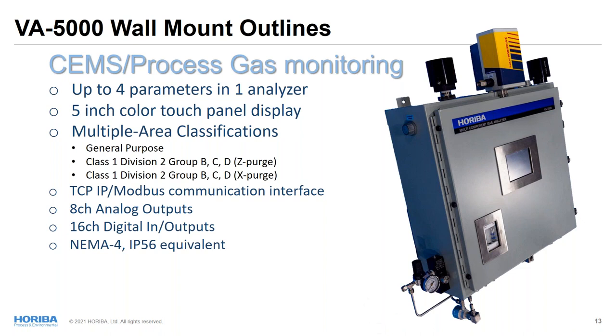All right, so the VA-5000 can measure up to 4 parameters with 1 unit, and it can be installed in multiple areas, including the general purpose area and Class 1 Div 2 Group BCD. Class 1 Div 2 can select from a Z purge type and X purge. X purge is selected when flammable hydrocarbon is present in the sample. Other than that, Z purge will work for the Class 1 Div 2 area, generally speaking. For your interface, TCP/IP and Modbus communication is available. Analog and digital inputs and outputs are available too, right there. And the standard cabinet is NEMA 4 and IP56 equivalent.